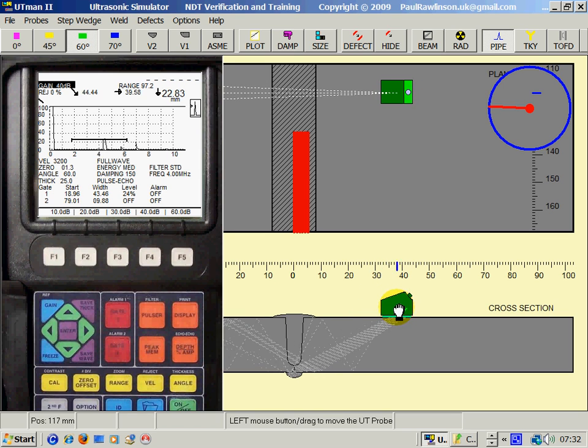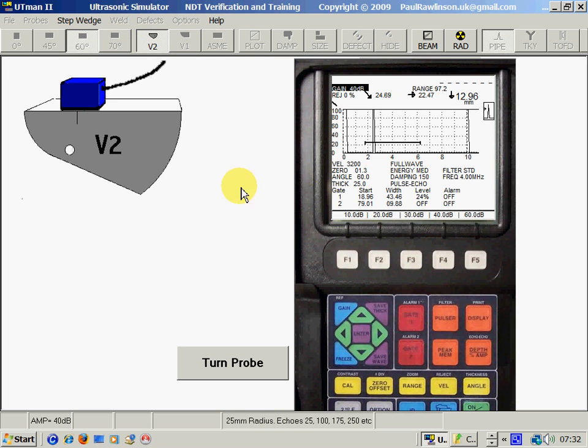Now, what I'm going to do now is take it back to the calibration block, which is the V2. I'm going to look at the readings here. The distance here says 24.69. It should be 25. To get it exactly right, I'm going to change the velocity. Now I'm changing the velocity, and these readings are changing. This distance should be 25 millimeters exactly. There.